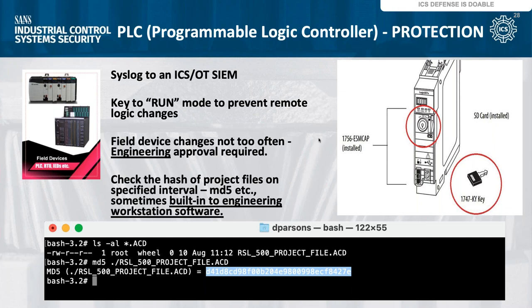In general, any changes to a device in the field should come with engineering approval, and very simple things, as you see on screen, like checking the hash of the project file - that logic code we talked about early on that runs inside the PLC. If you just take a hash of those project files for your critical PLCs in your plant, site by site, you can very quickly determine if anything has been tampered with or changed inside the PLC.